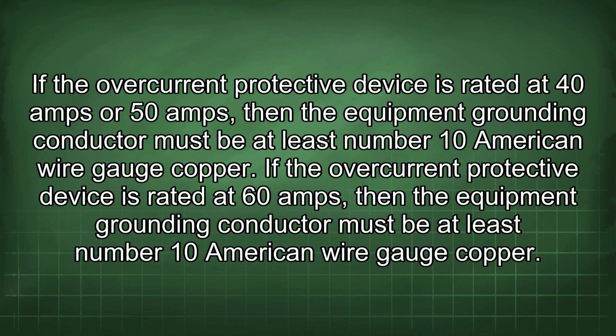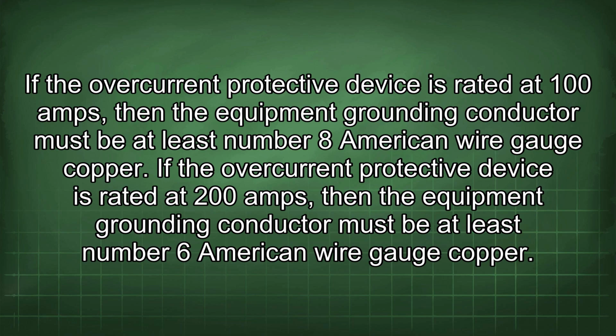If the overcurrent protective device is rated at 60 amps, then the equipment grounding conductor must be at least number 10 American wire gauge copper. If the overcurrent protective device is rated at 100 amps, then the equipment grounding conductor must be at least number 8 American wire gauge copper. If the overcurrent protective device is rated at 200 amps, then the equipment grounding conductor must be at least number 6 American wire gauge copper. If the overcurrent protective device is rated at 300 amps, then the equipment grounding conductor must be at least number 4 American wire gauge copper.